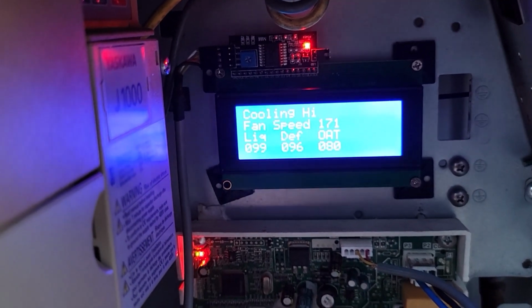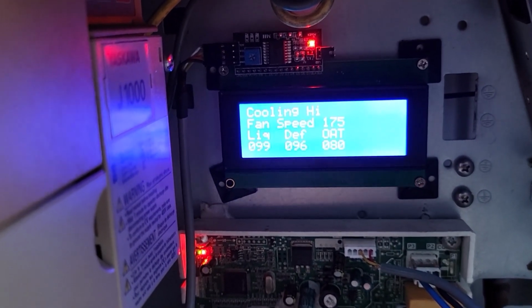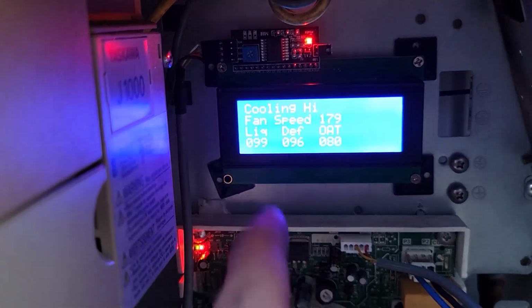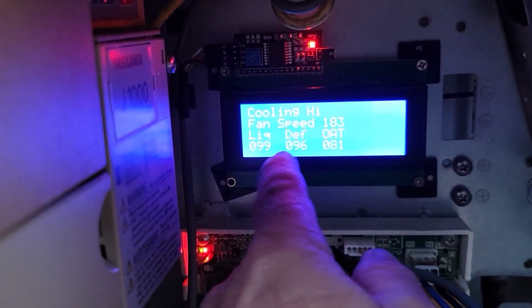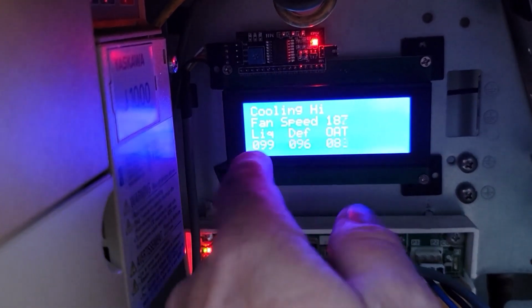So save, that's locked in the EEPROM. So if I take the power off and back on, it's going to remember that. See now, because I'm above the range, I have it modulating, it's still increasing speed, so this fan's actually speeding up now a little bit.